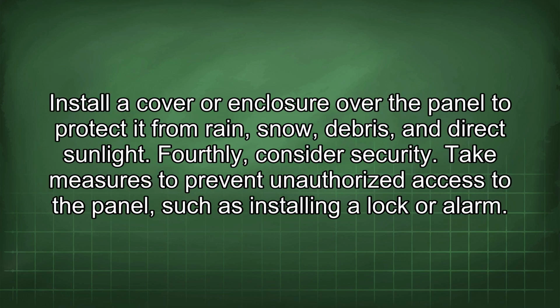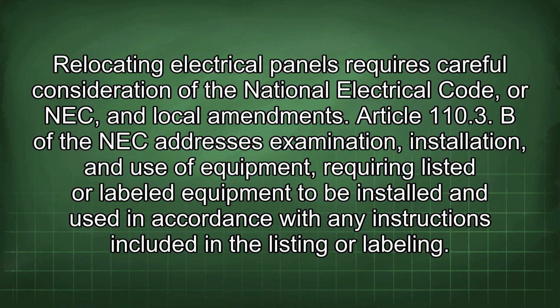Install a cover or enclosure over the panel to protect it from rain, snow, debris, and direct sunlight. Fourthly, consider security. Take measures to prevent unauthorized access to the panel, such as installing a lock or alarm. Relocating electrical panels requires careful consideration of the National Electrical Code, or NEC, and local amendments. Article 110.3 B of the NEC addresses examination, installation, and use of equipment, requiring listed or labeled equipment to be installed and used in accordance with any instructions included in the listing or labeling.